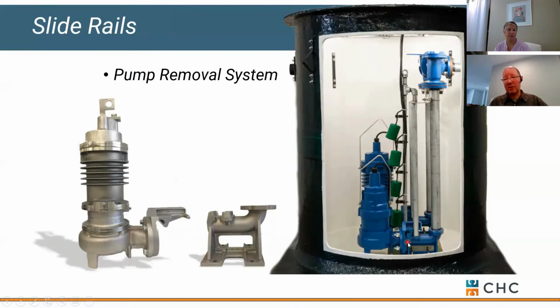So there might be a little leakage here. Remember, we're talking pump efficiencies that aren't very high. So it's possible you might get some leakage, but essentially that's a friction fit. And when you go to remove the pump, you simply grab the stainless lift cable that's usually anchored or zip tied near the cover. You grab that, you start lifting up on the pump. The first thing that happens is the pump tips in towards the guide pipes and kind of breaks this friction fit. And then as you continue to lift up on that cable, the pump simply rides up on these guide pipes. It's not till it's free that the pump will kind of swing around.